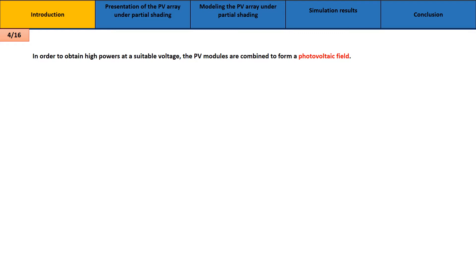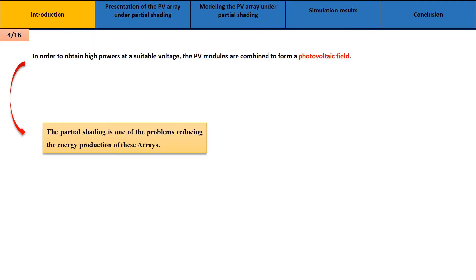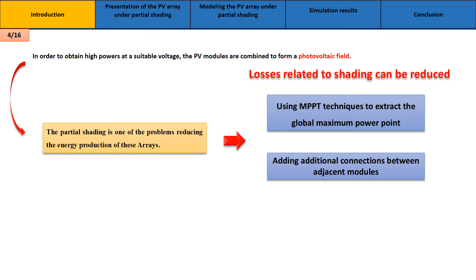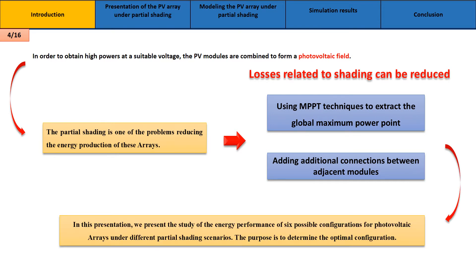In order to obtain high powers at suitable voltage, PV modules are combined to form photovoltaic arrays. However, partial shading is one of the problems reducing the energy production of these arrays. Losses related to shading can be reduced by using MPPT (Maximum Power Point Tracking) techniques to extract the global maximum power point, or by adding additional connections between adjacent modules.